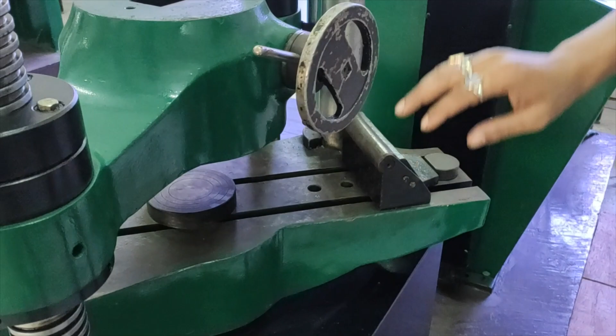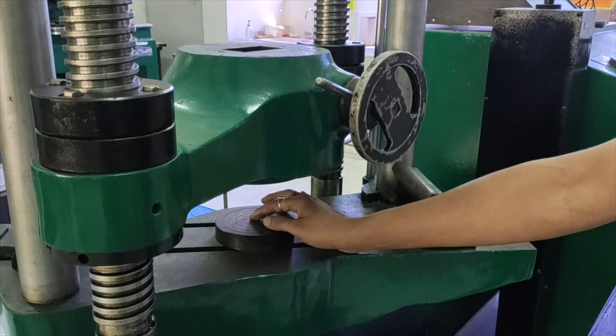This is the lower crosshead, this is the upper crosshead, and this is the table. For tensile testing this space will be used, and for compression testing and 3-point bend testing we have different fixtures. One plate will be attached here, and already one plate is available here, so we will put our compression test specimen and compress it.